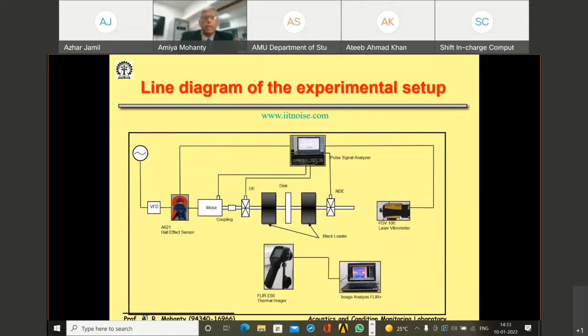We are trying to focus on the bearings to see them get heated up. So what we did in this rig, we tried to put different couplings between the motor and the shaft: rigid coupling, helical coupling, gear coupling, etc. And we artificially created misalignment between the shaft and the motor shaft here, with the shaft carrying the bearings, the bearing loader, and the motor shaft. And we monitored the temperature at the NDE bearing.